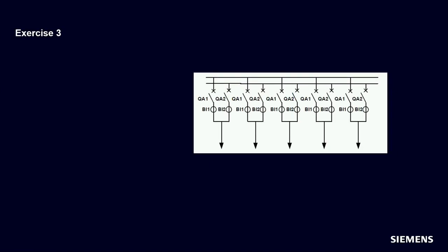Exercise 3 may be also quite interesting. First of all, how many bus zones do we need? I think this could be answered quite fast. Of course, we need 2 bus zones. Do we need a disconnector image? Maybe quite interesting, because it looks a little bit like a double busbar, as we have 1 bus section on the top, and below we have a further bus section. But please look carefully. I can't find any feeder CT which could be assigned to different bus zones. So we need no disconnector image. We have no busbar disconnectors.